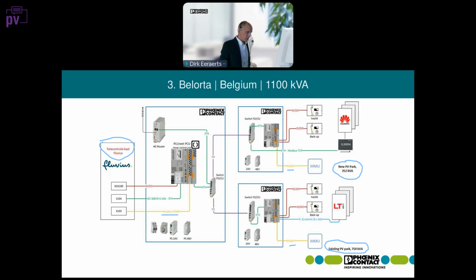The control commands come into the PCU, and from there over fiber, because the distance between the main cabinet and the elements in the field, so the inverters, is quite large. So we have remote IOs with a fiber connectivity between those cabinets. And then from the remote IO, we will then convert the signals back to digital signals, or we will be able to receive the RS485 signal and convert that to Ethernet over fiber.